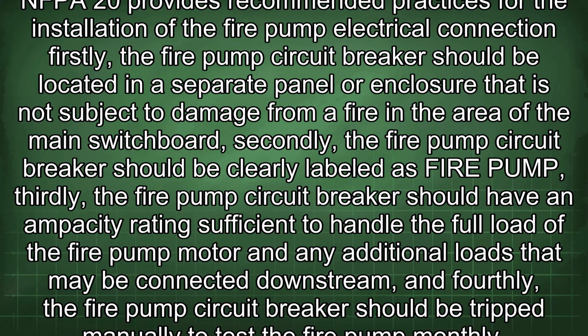Thirdly, the fire pump circuit breaker should have an ampacity rating sufficient to handle the full load of the fire pump motor and any additional loads that may be connected downstream. And fourthly, the fire pump circuit breaker should be tripped manually to test the fire pump monthly.